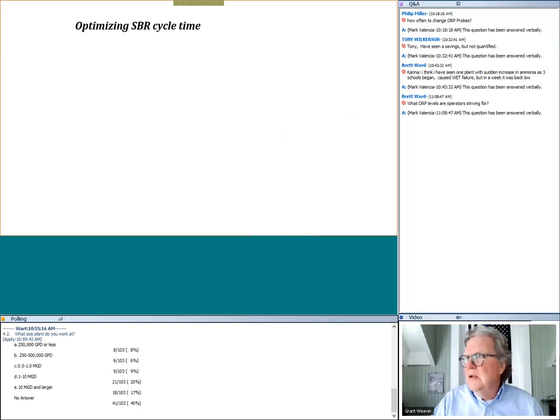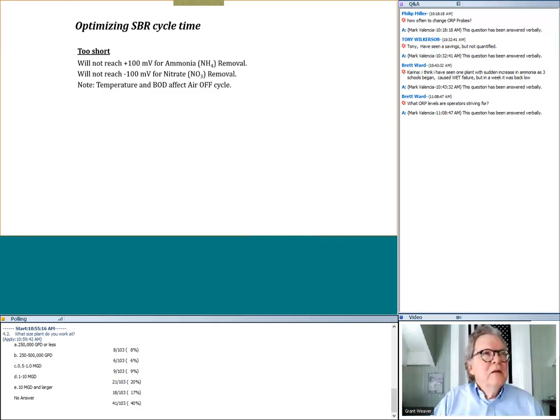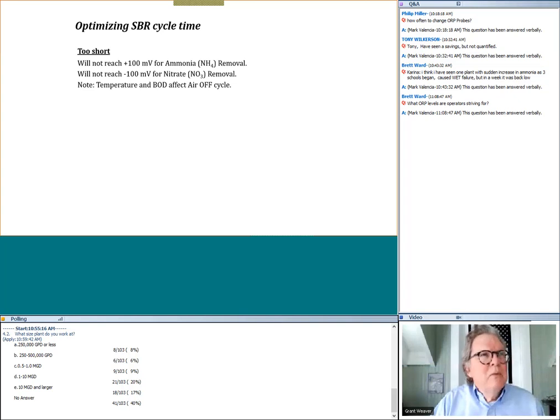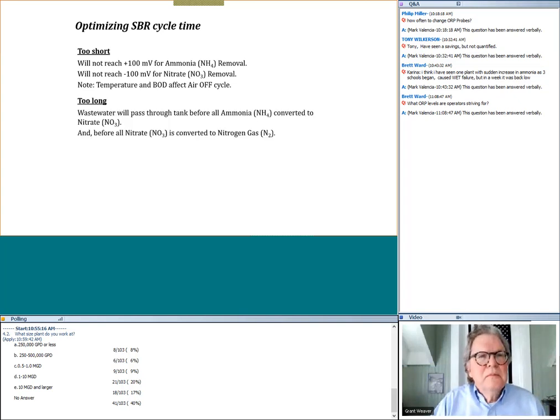As Karina said, I do like crunching numbers. So for me, I would like to put an ORP in the tank. I'd like to track the ORP every 5 to 10 minutes. And then I'd like to plot it. And I want to see that it's getting up to my positive 100, positive 150 even. And then that it reaches down into the minus 100. And I would want to correlate those numbers with what the effluent looks like, which would be my way of truing up those numbers.